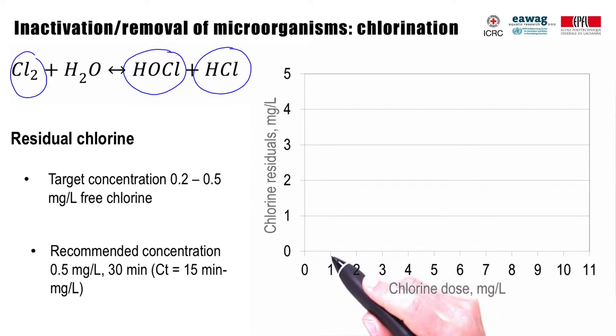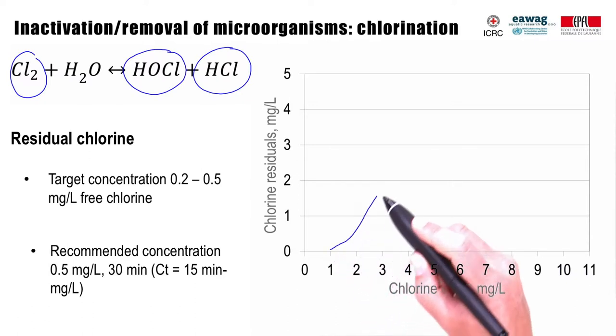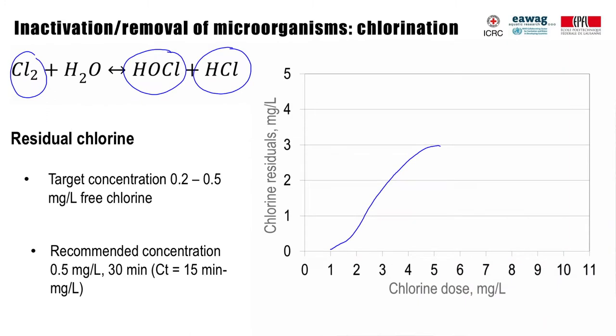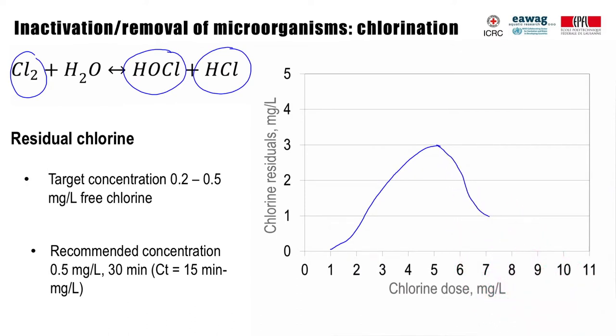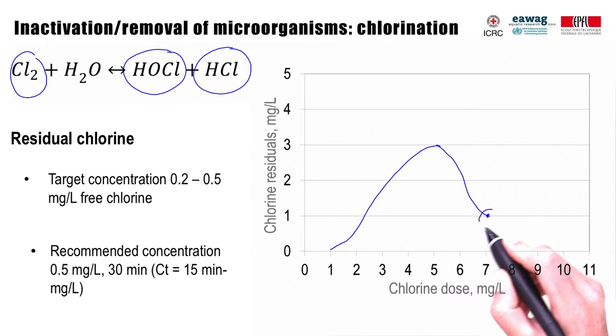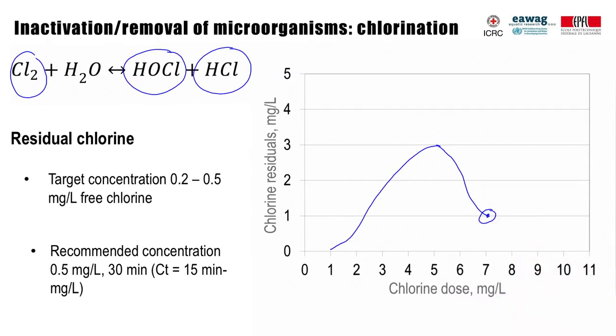If you look at this figure, we can see that at first the chlorine residual will increase proportionally to the amount of chlorine added, until the mole ratio of ammonia to chlorine is about 1. Beyond that, additional chlorine reduces total chlorine residual due to oxidation of some chloramine species. The breakpoint is the point at which complete oxidation of all chloramine species occurs. Its location depends on the presence of organic matter, nitrogen and reduced inorganic ions. After the breakpoint is reached, free chlorine residual increases proportionally with the chlorine dose.